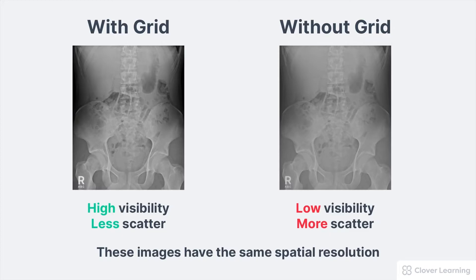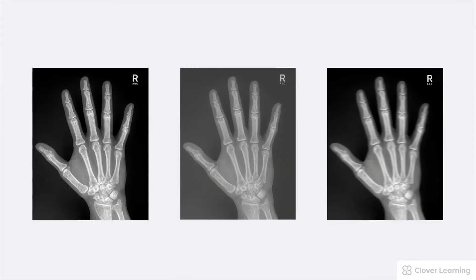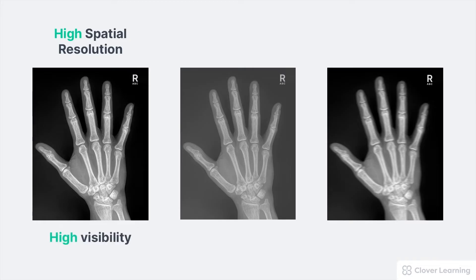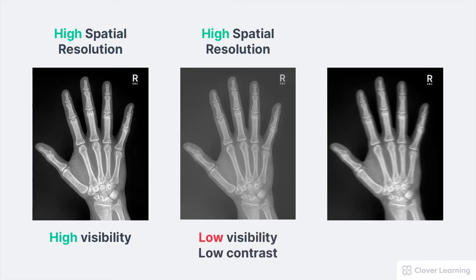It might be easiest to understand the definition of spatial resolution by thinking of one of the most common causes of poor spatial resolution, which is motion. The first image in this series shows very sharp structural lines, so high spatial resolution. The sharpness of the structural edges is very visible, so that's high visibility. The second image still has a high level of spatial resolution recorded in the image, but poor contrast has made the structural sharpness difficult to see. The last image shows very blurry structural lines because of motion — that's low spatial resolution because the structural edges are not sharp at all.